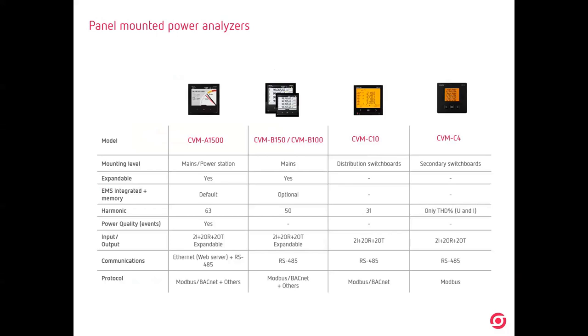We have one for secondary switchboards, which shows the total harmonic distortion, but not the harmonics individually. We have inputs and outputs for controlling relay and transistor output for controlling the installation. We have communications, and if you need more features, you have to move to the left. We move from CVM C4 to C10, B100, B150, or A1500. C10 is for distribution switchboards, also with communications, input outputs, Modbus/BACnet, and up to 31 harmonics.